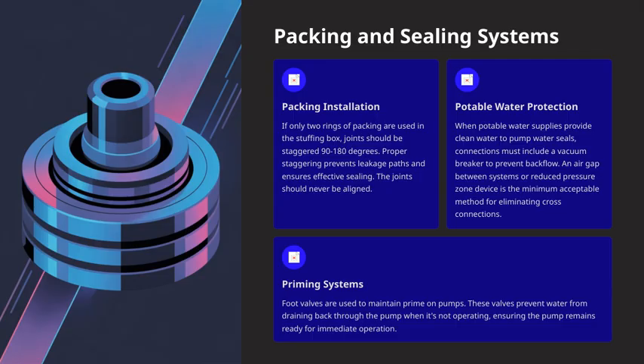Next, when it comes to potable water protection, if you're supplying clean water to pump water seals, you need to include a vacuum breaker in the connection. This is crucial because it prevents backflow, which could contaminate the potable water supply. The simplest and most effective method is to have an air gap between the systems or use a reduced pressure zone device, both of which eliminate cross connections and help maintain water safety.